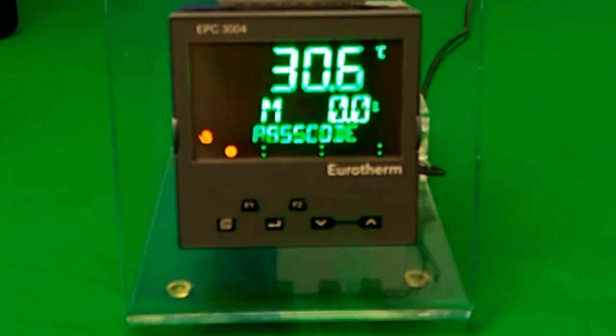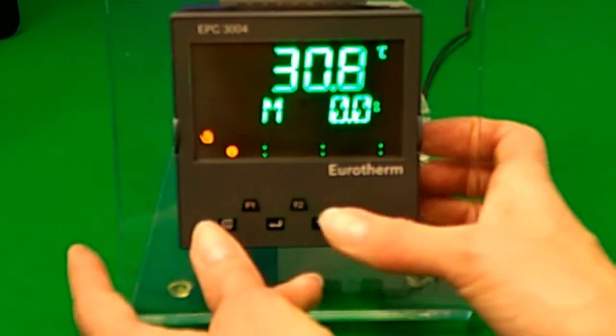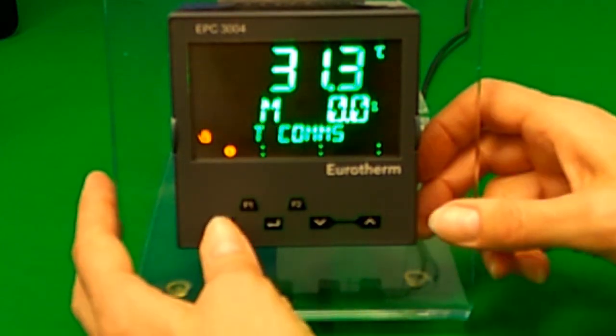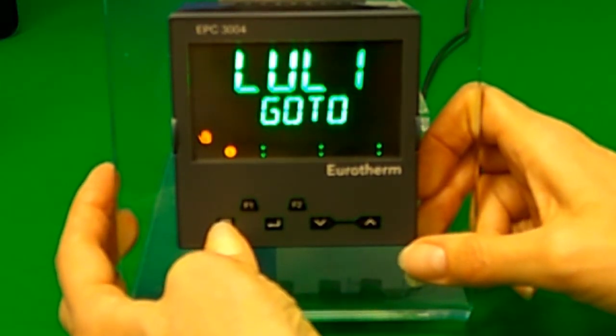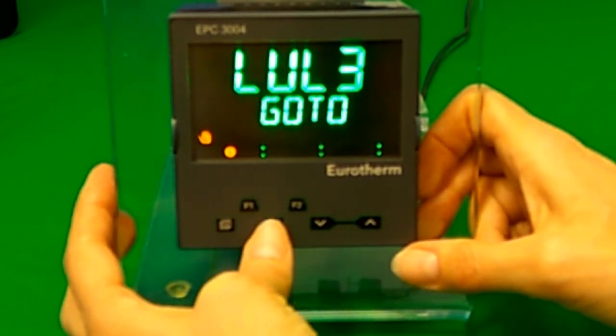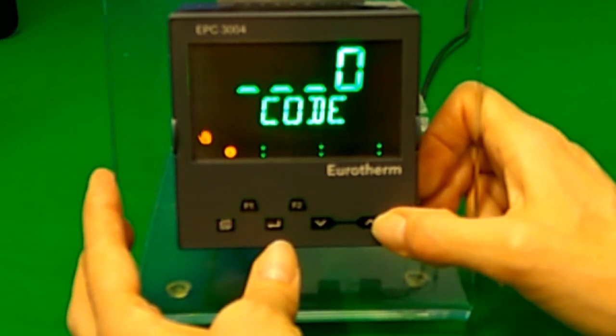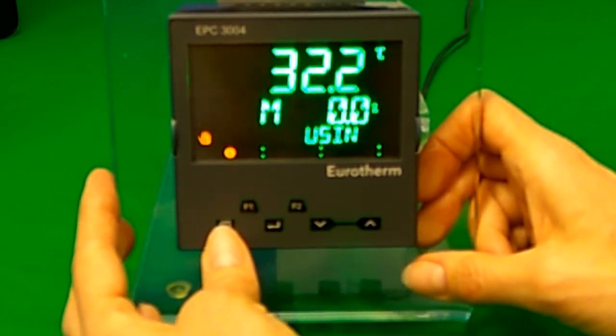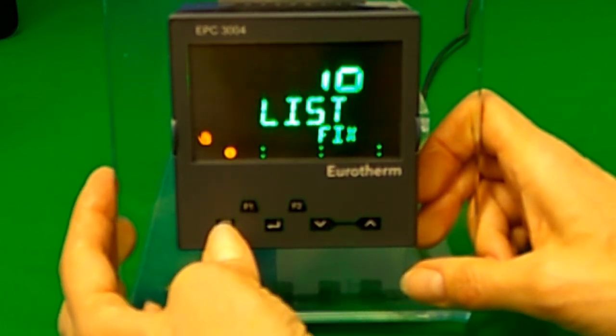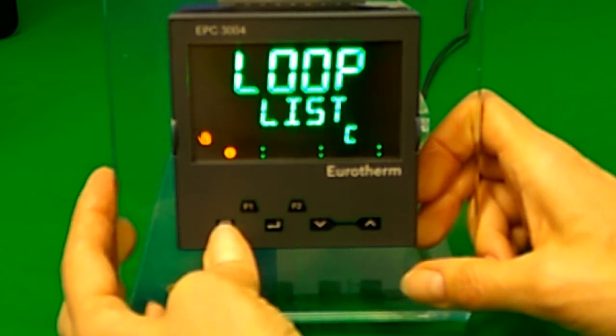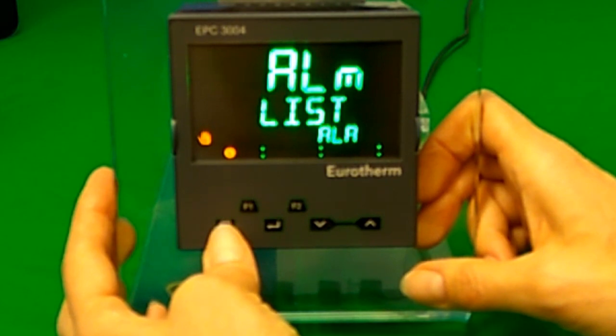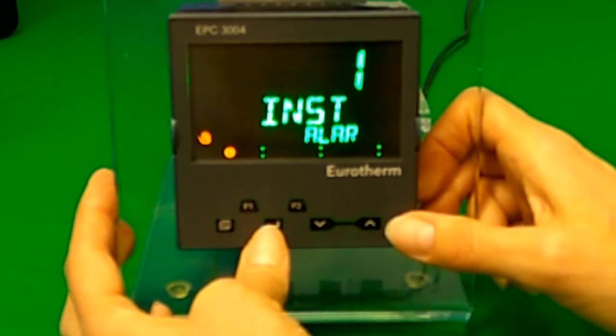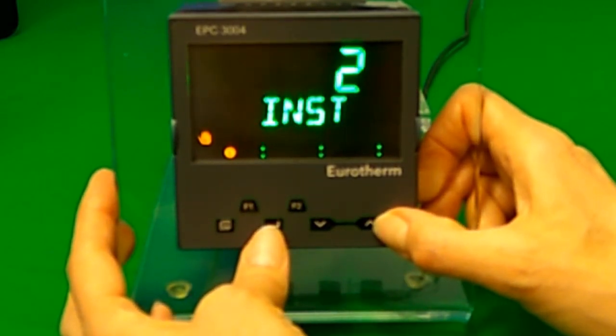This function is configurable. If the configuration in use does not have the shortcut of page and scroll together, it will be necessary to go to the alarm by entering level 3, and then pressing the page button until you get to alarms. Then press the scroll button, and then the up button to get to the relevant alarm number.